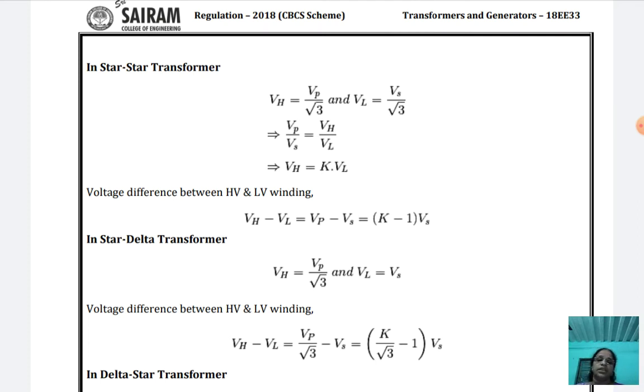But what is the star delta transformer? Star delta means the HV side is star connection and the LV side is delta. In delta, the line voltage is equal to the phase voltage. In star connection, the phase voltage is equal to VL by root 3. VH means the star side, that is the HV side, and VL means delta. So the voltage difference between the HV winding and the LV winding is VH minus VL, same as before, but with VP by root 3 minus VS, finally we get (K divided by root 3 minus 1) into the secondary voltage. Compare this with the star transformer formula, (K minus 1) into the secondary voltage. Here it is (K divided by root 3 minus 1) into VS.